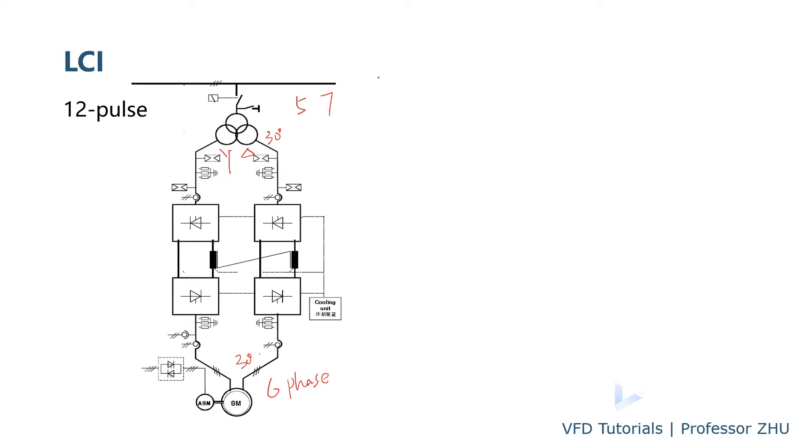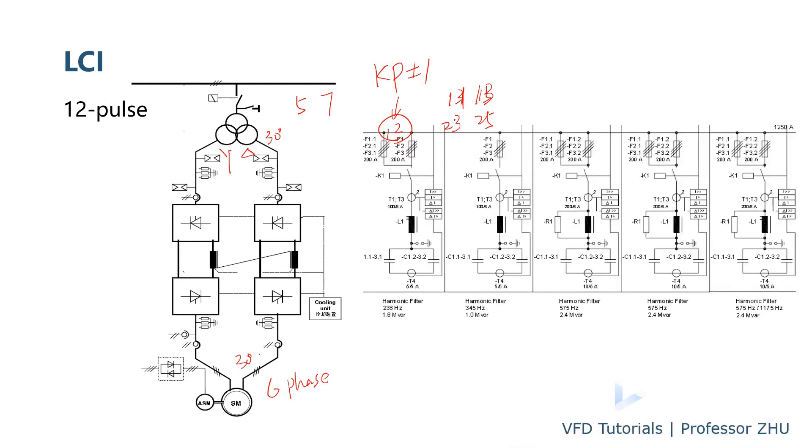In order to reduce the harmonic, people use two sets of LCI to drive the motor. The motor can use a six phase motor with two sets of winding and a 30 degree phase shift to cancel some of the torque ripple harmonics on the motor side. And on the line side, you will use three winding transformer. So the secondary of transformer will be one with the Y, another with the delta, and a 30 degree phase shift. So a lot of harmonics will be canceled by this kind of multi-pulse rectifier.